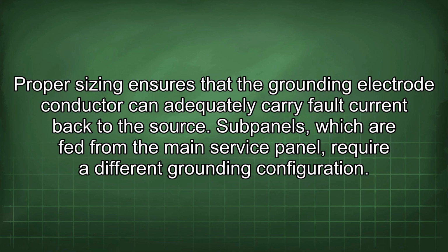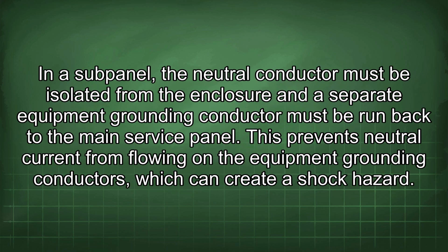Subpanels, which are fed from the main service panel, require a different grounding configuration. In a subpanel, the neutral conductor must be isolated from the enclosure and the separate equipment grounding conductor must be run back to the main service panel. This prevents neutral current from flowing on the equipment grounding conductors, which can create a shock hazard.